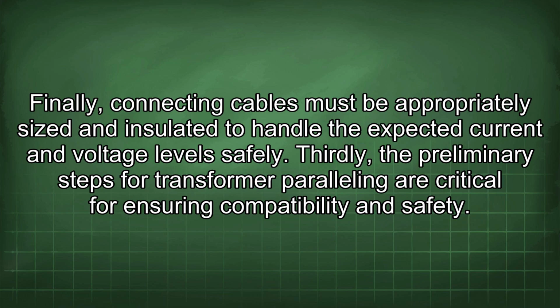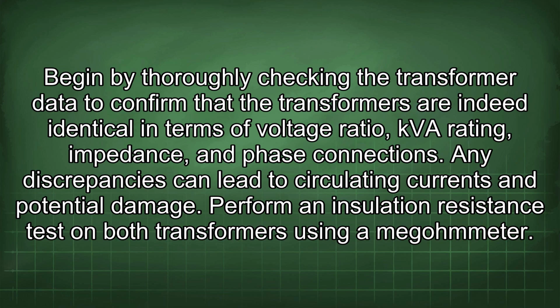Thirdly, the preliminary steps for transformer paralleling are critical for ensuring compatibility and safety. Begin by thoroughly checking the transformer data to confirm that the transformers are indeed identical in terms of voltage ratio, kVA rating, impedance, and phase connections. Any discrepancies can lead to circulating currents and potential damage.